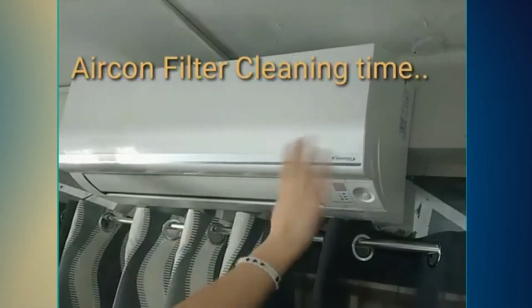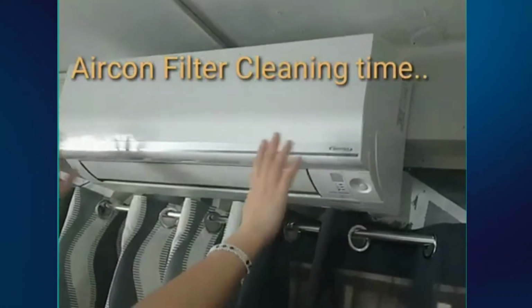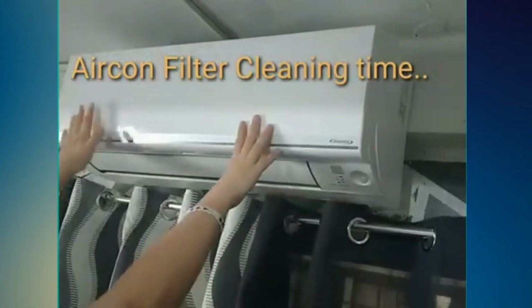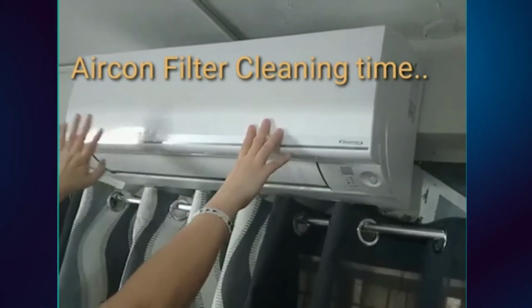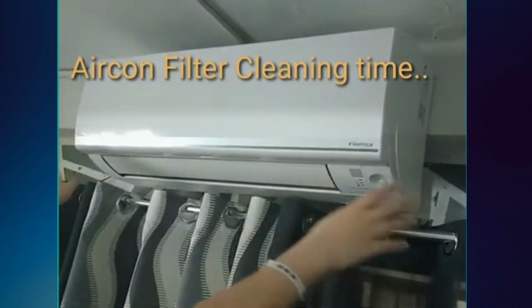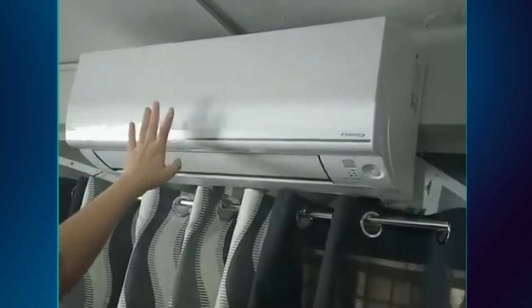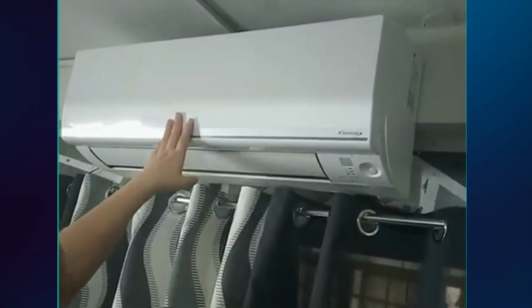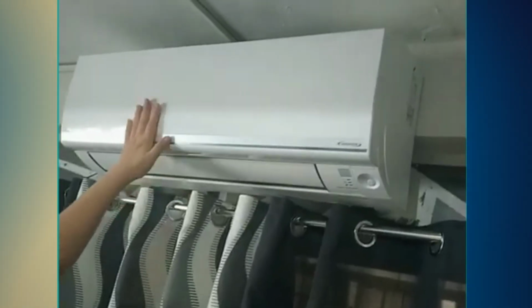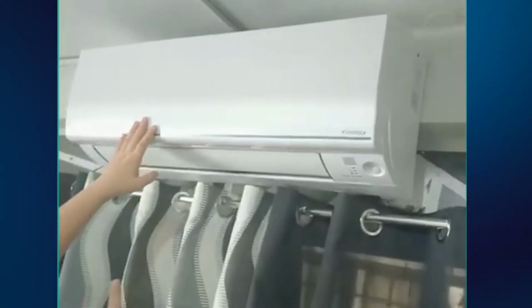Today, I'm going to show you how to clean the air filters in a wall-mounted Daikin air conditioner. A dirty filter restricts airflow and can reduce the unit's cooling or heating performance. The air conditioner may need to run longer, use more electricity, produce weaker airflow, or develop unpleasant odors.